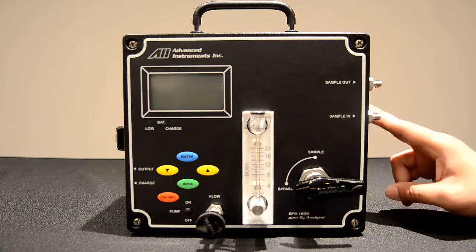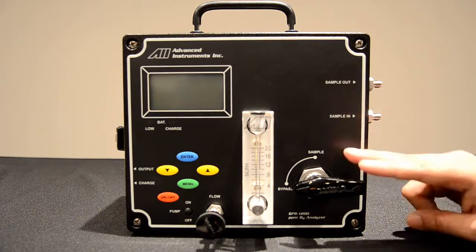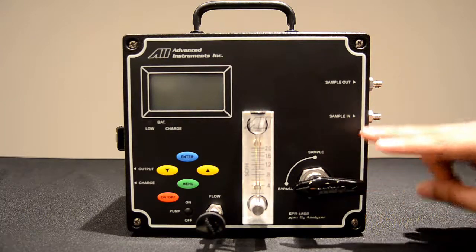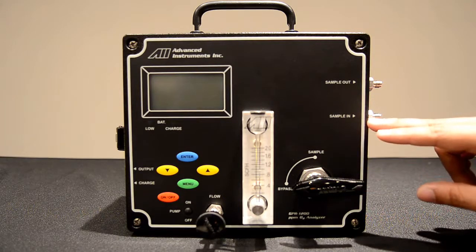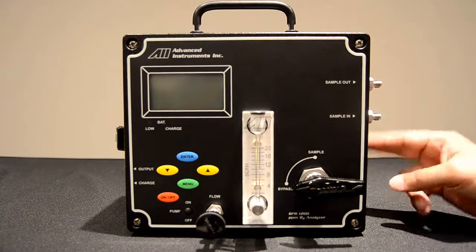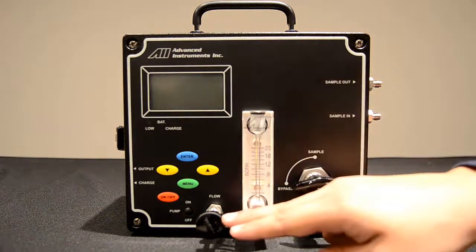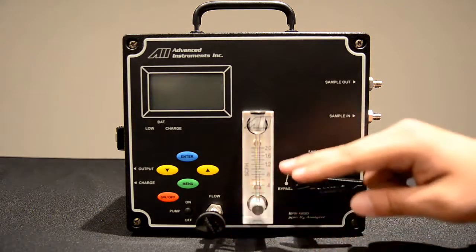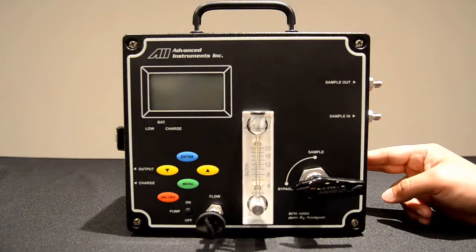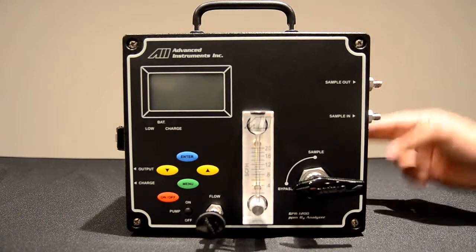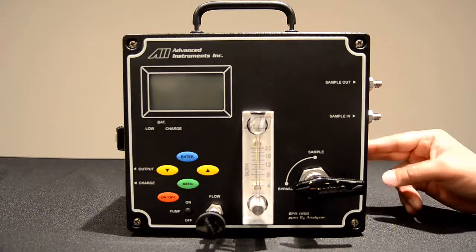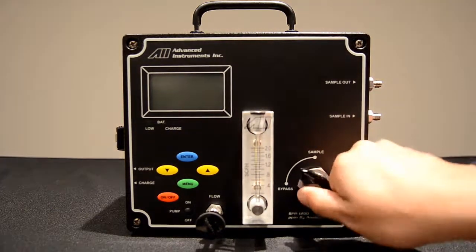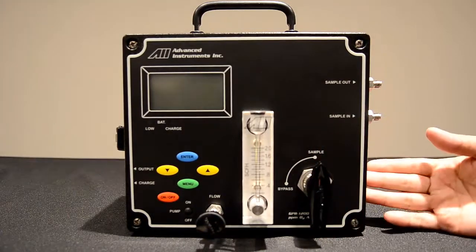During storage and transportation the analyzer will be in bypass mode. You'll connect at the sample inlet and flow your gas through the analyzer. You'll adjust the flow rate with the flow valve and we recommend a flow rate of 1.5 SCFH. Once flow has been established to the analyzer and has been purged out for a few minutes, you will switch from bypass to sample.